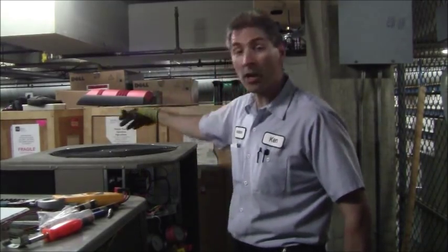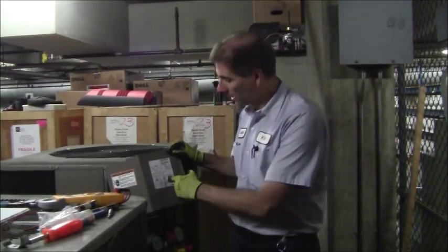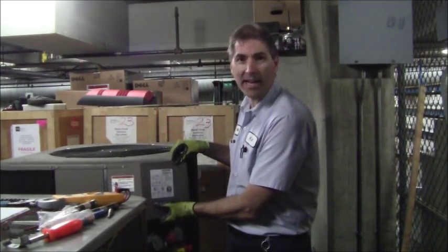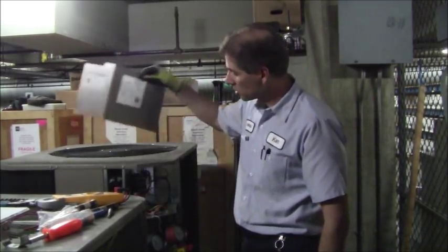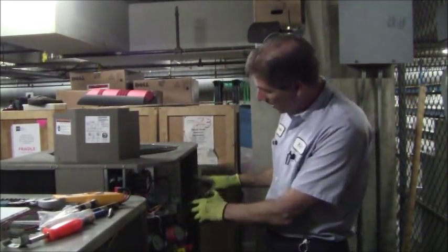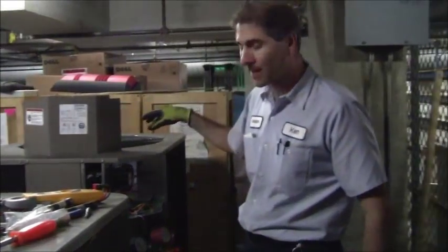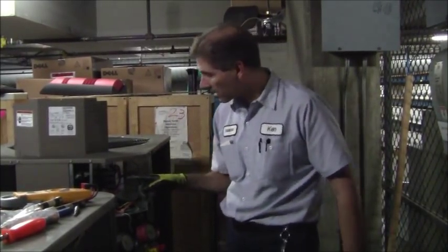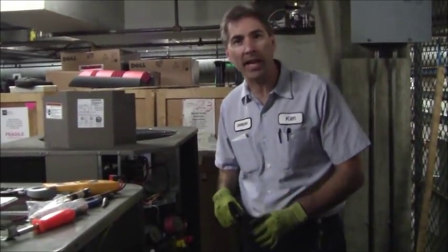So I know that the thermostat is calling, so I want to see what's going on in the electrical section here. There are some 5/16 inch head tech screws that hold on this cover plate. I pull that off, and then I'm exposed to the electrical. Then you can see the contactor, and I can see the capacitor for the condenser fan motor right here. This particular unit is a 3-phase unit, 460 volt. Now, when I look at the contactor, I can see that the contactor is pulled in, and I'll show you that.